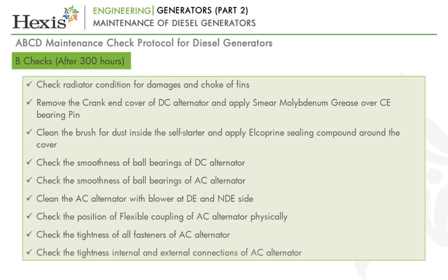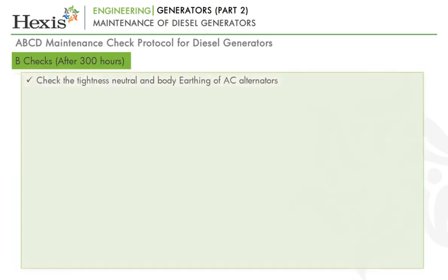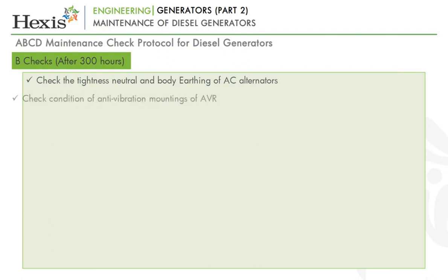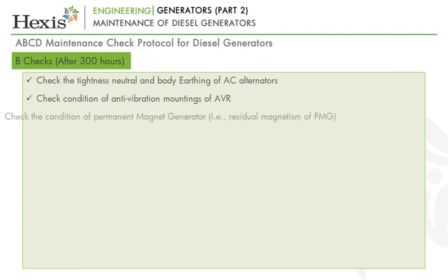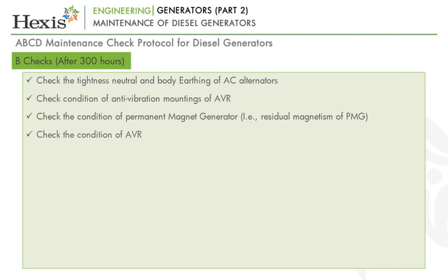Check the tightness of internal and external connections of AC alternator. Check the tightness of neutral and body earthing of AC alternators. Check condition of anti-vibration mountings of AVR. Check the condition of permanent magnet generator, that is residual magnetism of PMG. Check the condition of AVR.